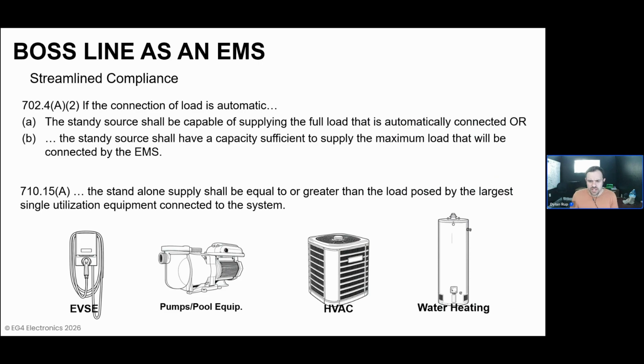So it requires our partners a lot of times to either be forced into installing a critical load subpanel or way more inverters than they should realistically need to power that home reliably. However, the alternate path is to install an energy management system, essentially a system that can shed some of the heavy consumers to ensure that the continuous output of the system now is rated to power the automatically connected load of the system.